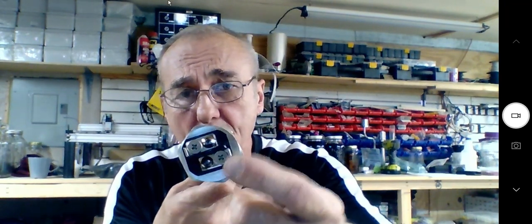All elements also, you'll notice on the bottom, have only two screws. You'll see there's one there, and then there's one there. They are not polarity specific, which means that it doesn't matter which wire you put on there, the screws don't care. For 120 volts, you'll have a hot wire going in, and you'll have a neutral wire on the other side. And if you understand the flow of electricity alternating current, which means it's high-low, high-low, high-low, so it's going in both directions, it makes no difference.